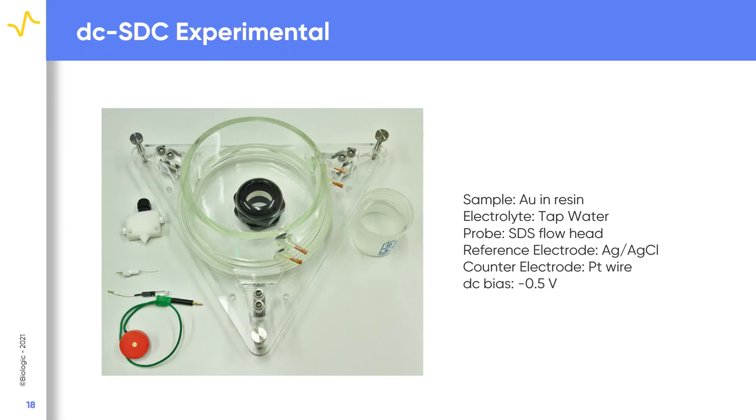When SDC measurements are performed on the SDS 470, what sort of data can be expected? In the following slides, we will show example results using the SDC flow head. We will first look at a DC-SDC measurement of the standard gold and resin sample. This is performed using tap water as the electrolyte. The sample is biased at minus 0.5 volts versus silver-silver chloride.